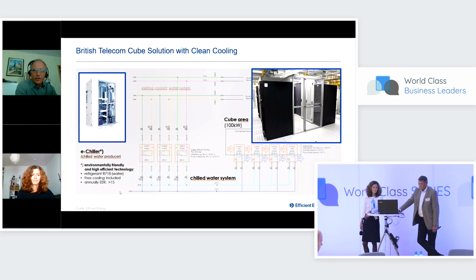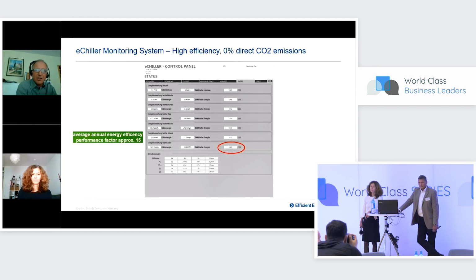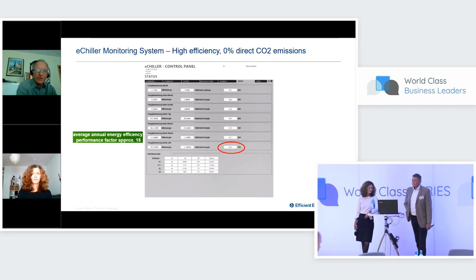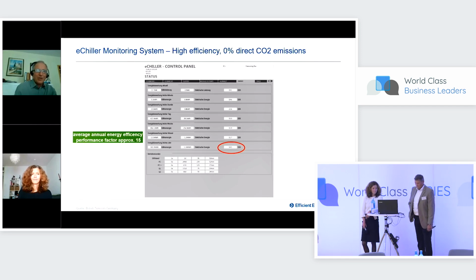By using water as a refrigerant at very low pressure conditions in the system, one is out of the strict regulations for applications with conventional refrigerants. This concerns procurement bottlenecks, costs, tests and documentation according to F-gas regulation, and tests according to pressure vessel regulation. Water is a climate neutral, neutral medium with a global warming potential of 0. In addition, since the maintenance cycle of the chiller is once a year, the effort and the operational costs are very low compared to other refrigeration systems. A maintenance contract with efficient energy is in place.